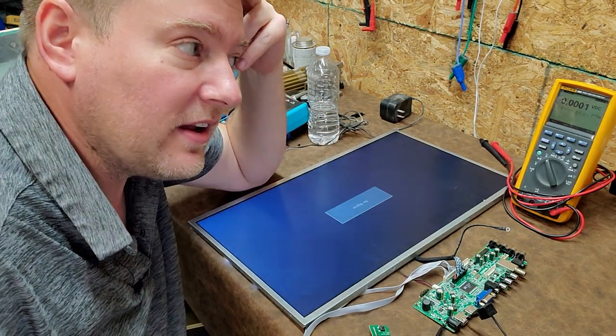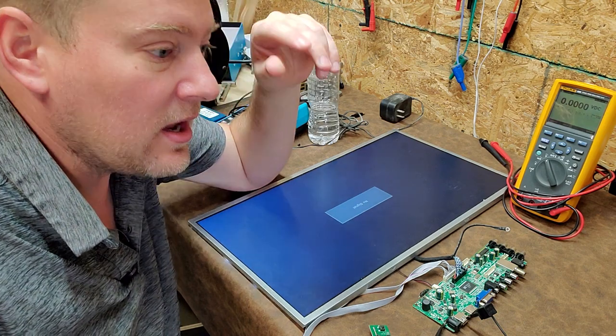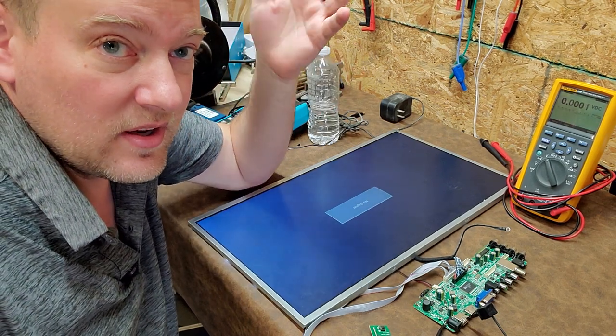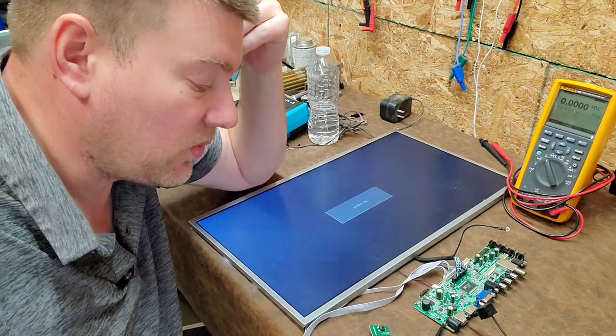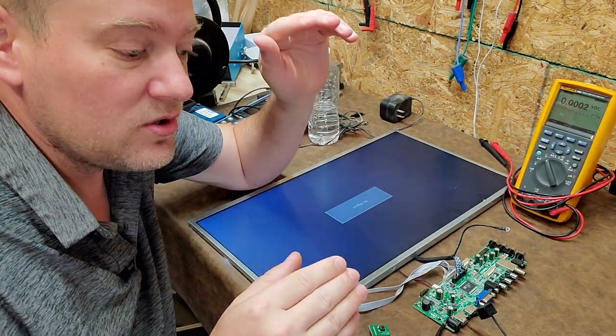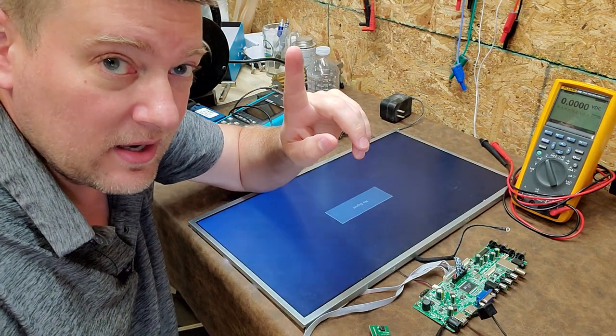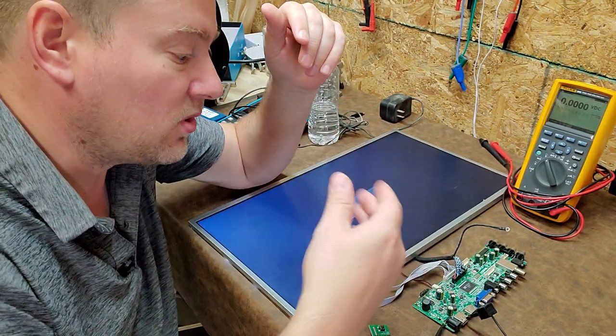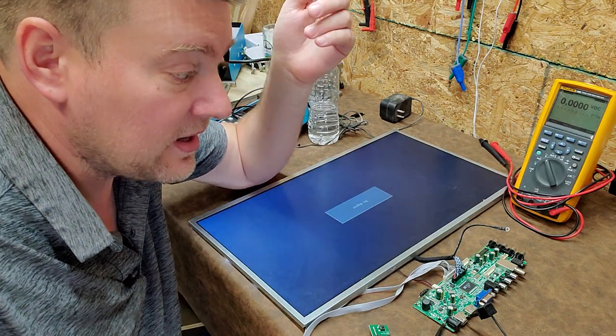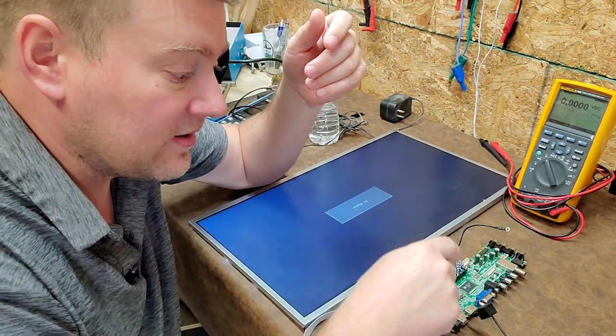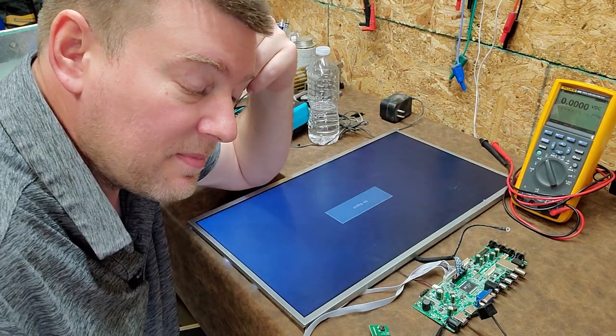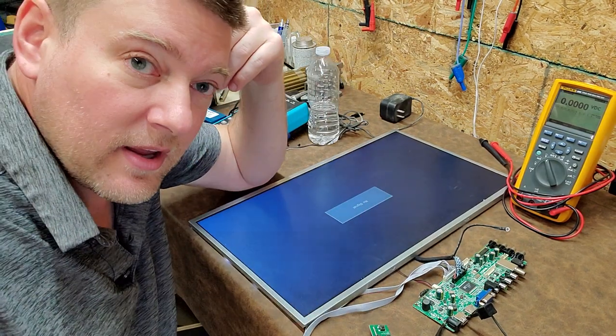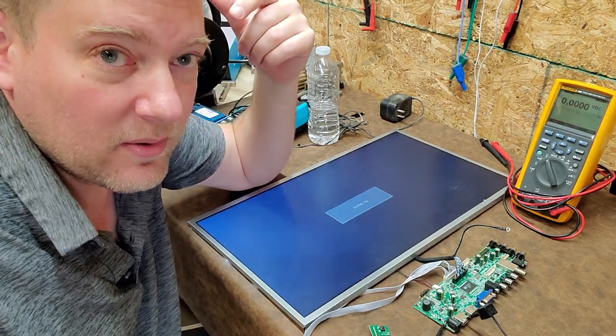But more than likely what they were experiencing is a problem with the power supply. The weak link on almost every single medical device is going to be your DC power supply. And that's because it's designed to be the weak link. Remember guys, just because you have voltage does not mean necessarily that you have current. So once you go to boot up a TV or something like this, it starts pulling that voltage, and if your DC power supply can't keep up, it drops below the threshold and it will not allow it to power on.